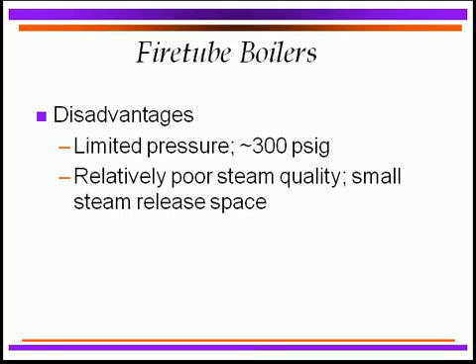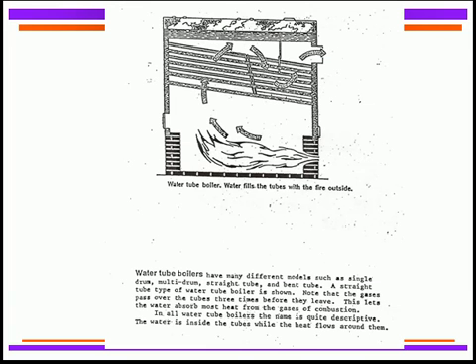The other area is that fire tube boilers have a limited steam area where the steam separation occurs from the boiler water. It's fairly small, so consequently the steam quality is not as good as it would be over a water tube boiler. We do have a concern about steam quality and usually don't use those type of boilers for driving turbines because of the poor quality of steam.